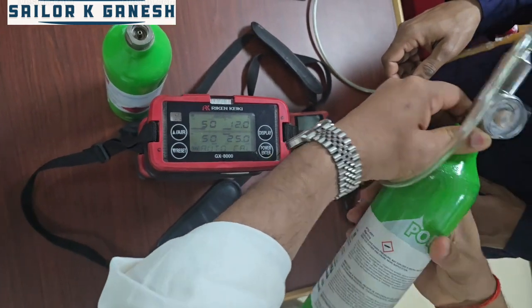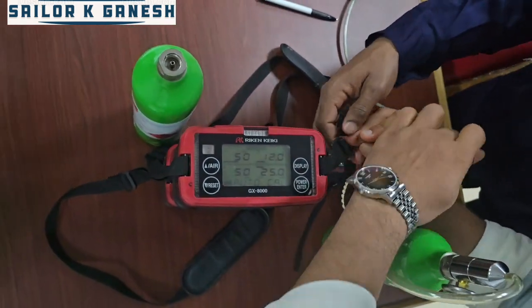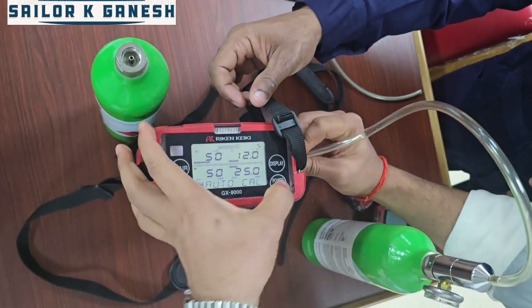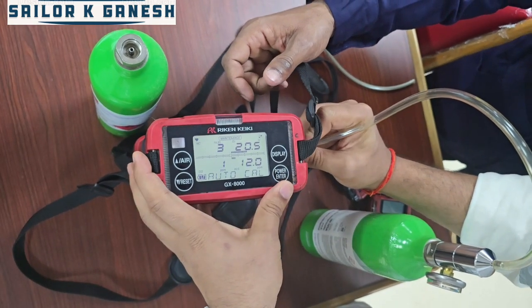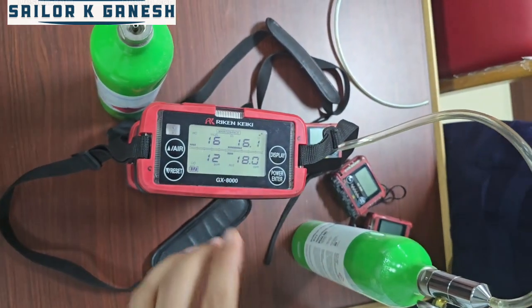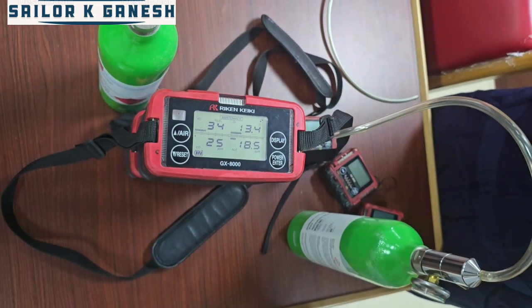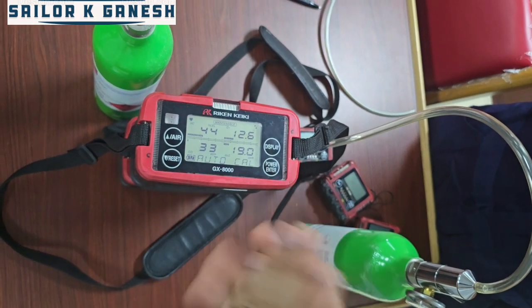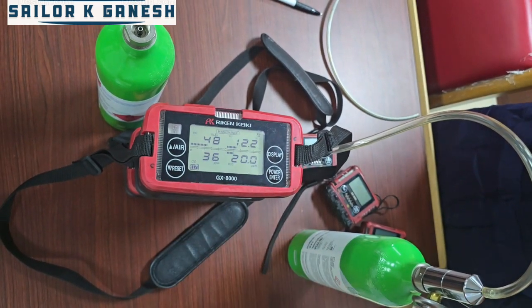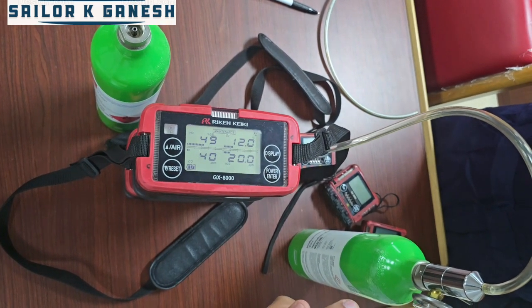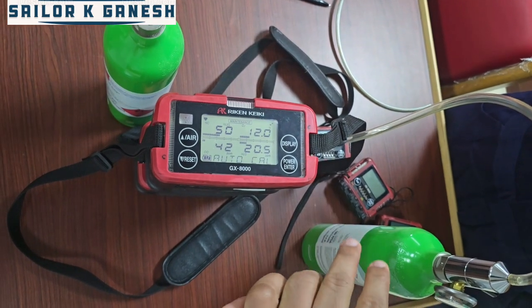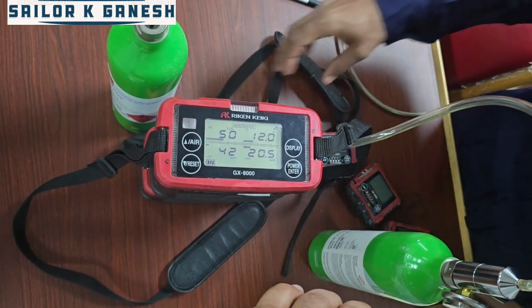Okay, now the valve is open. Now connect the gas and then press enter. Okay, now it has started sensing the gas. Since this is auto calibration, once it reaches that point, it will calibrate the equipment accordingly, and you will get to know once you press enter whether the test has passed or failed.